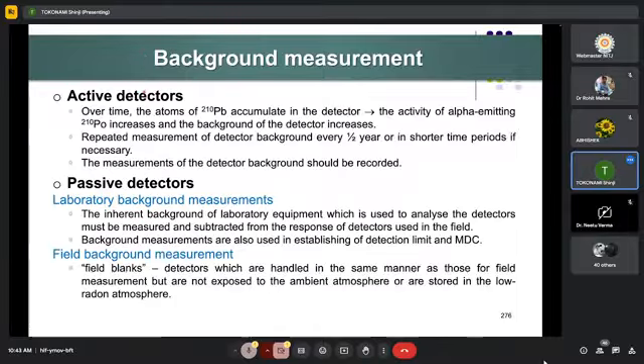Background measurement. In terms of active monitors, over time, atoms of lead-210 accumulate in the detector. And then the activity of alpha-emitting polonium-210 increases, and the background of the detector increases. Repeat measurement of detector background every half year or in shorter time periods if necessary. The measurement of the detector background should be recorded.